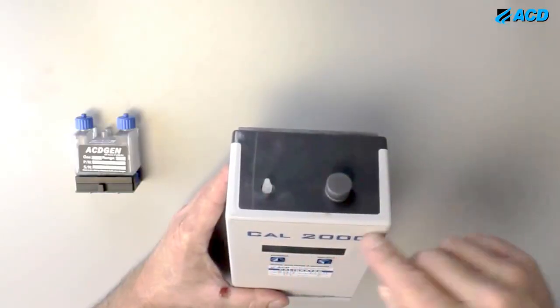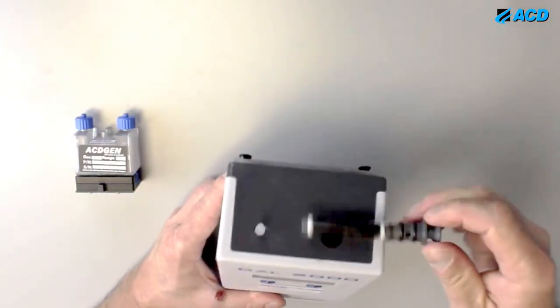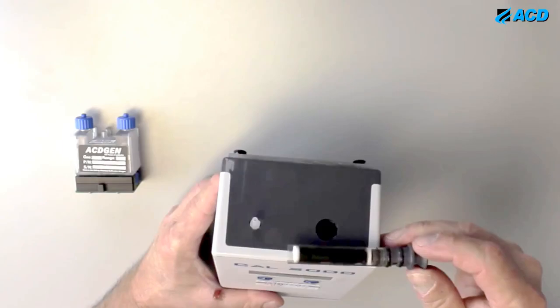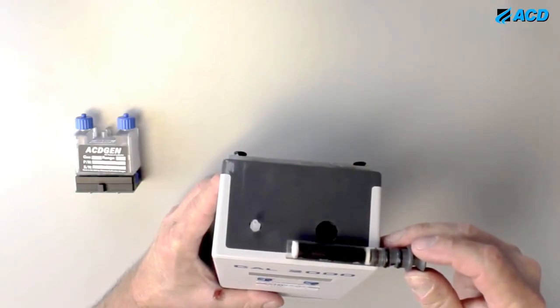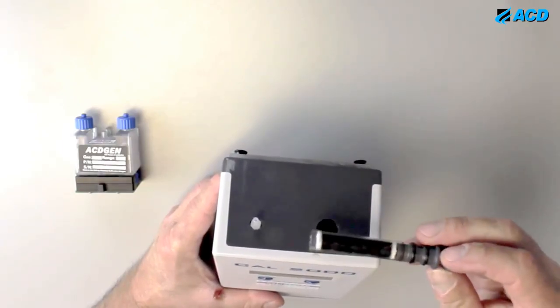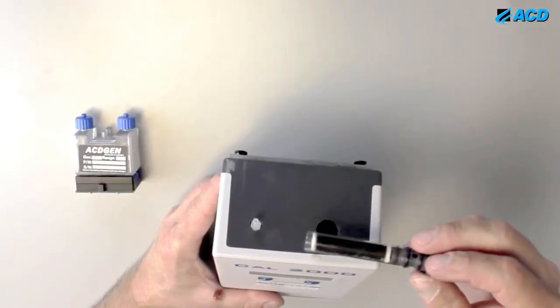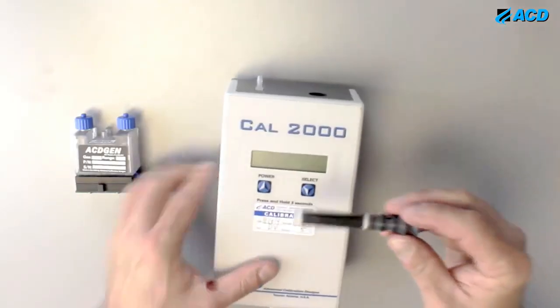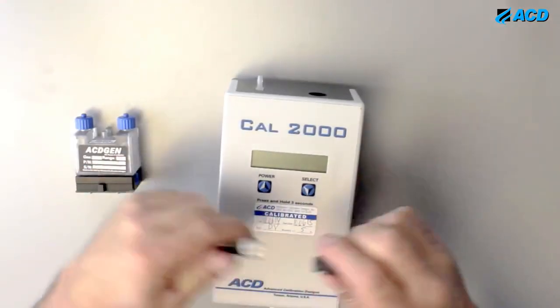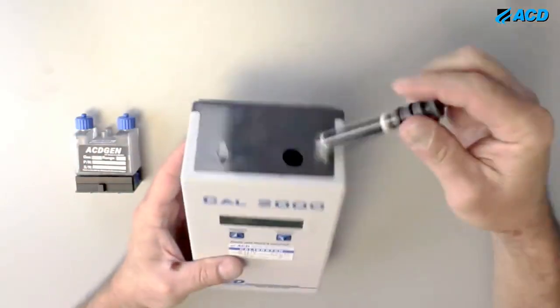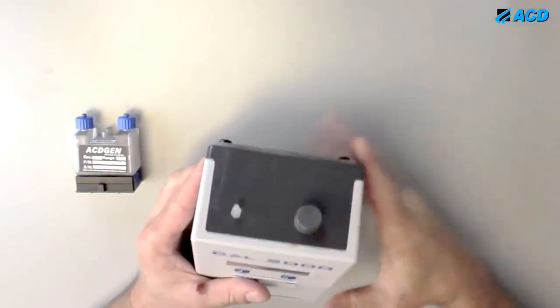It goes into a flow manifold and through a charcoal filter to scrub all the background air and make sure it's clean. If you work in a real dirty environment, we sell replacement charcoal filters. They just go on with an O-ring seal. You throw this one away, replace it, put it in, and again, O-ring seal it, just push it down into place.